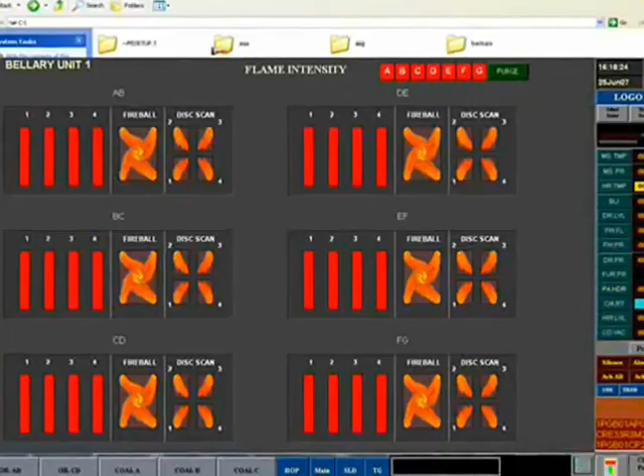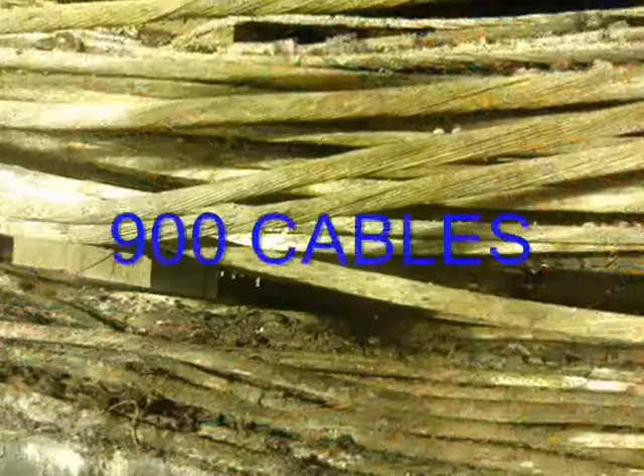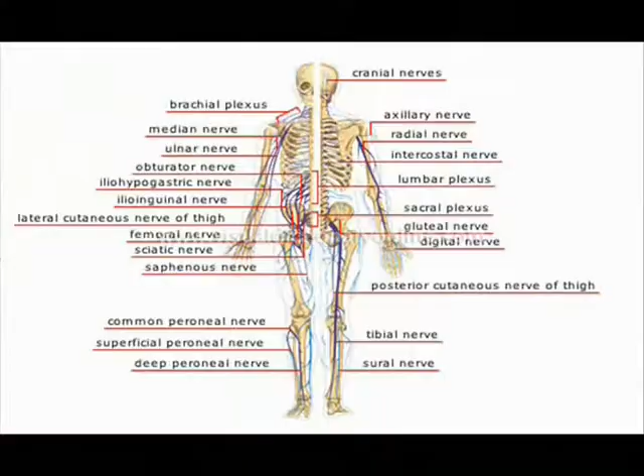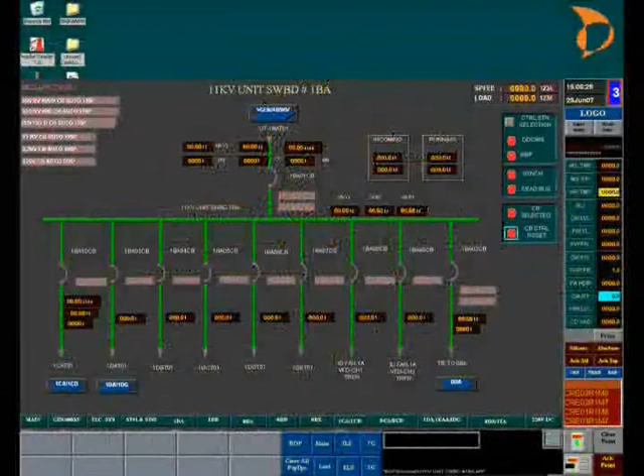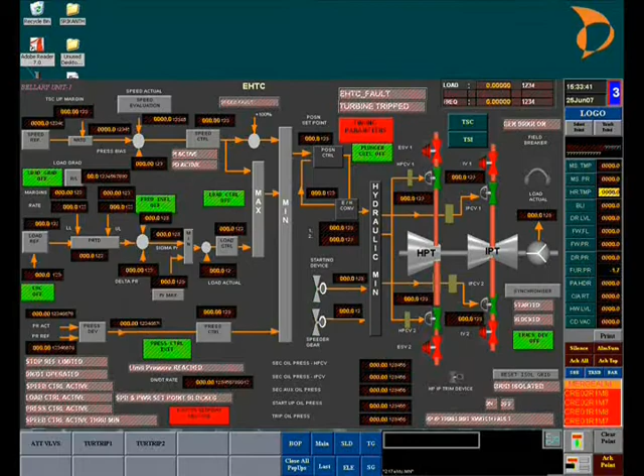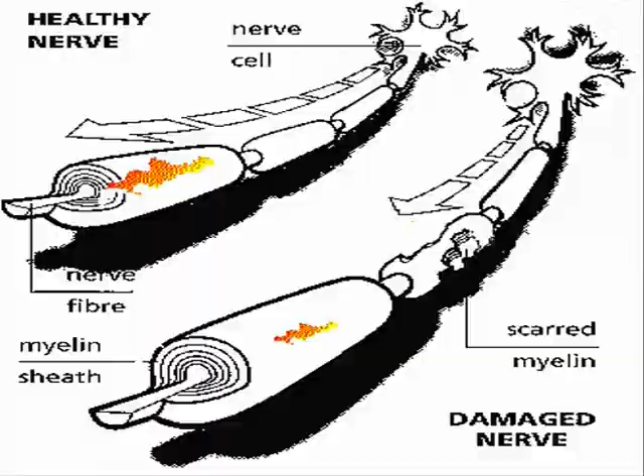In the cable vault, out of 6 cable trays, the 3 bottom perforated trays carried control cables. All of them were burnt badly. This was the first emergency of its kind for the instrumentation engineers. They estimated about 900 cables of the bottom 3 perforated trays were badly damaged. Part of the nervous system of the power station got hurt. The power plant automation system was in ICU. It was the rarest of rare cases in the history of power plant automation. Instrumentation engineers had a very challenging task, to repair the badly damaged nervous system of the plant.